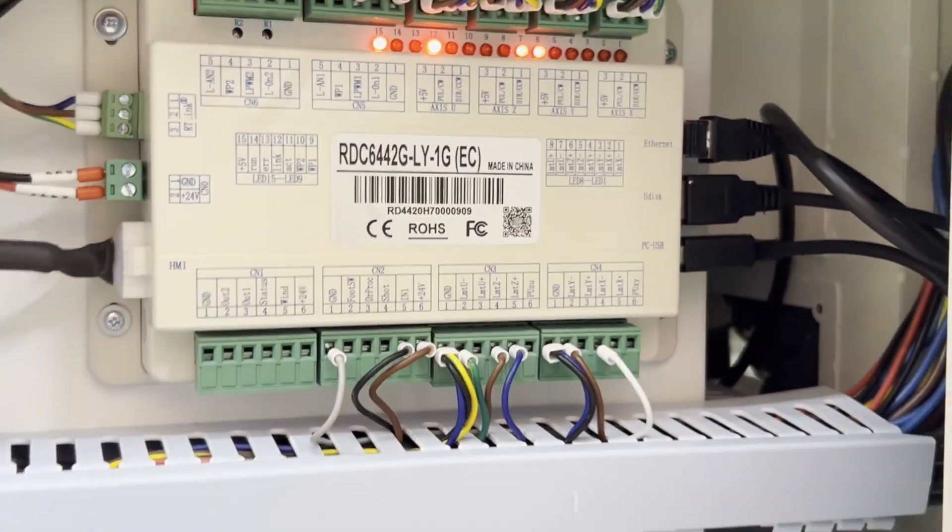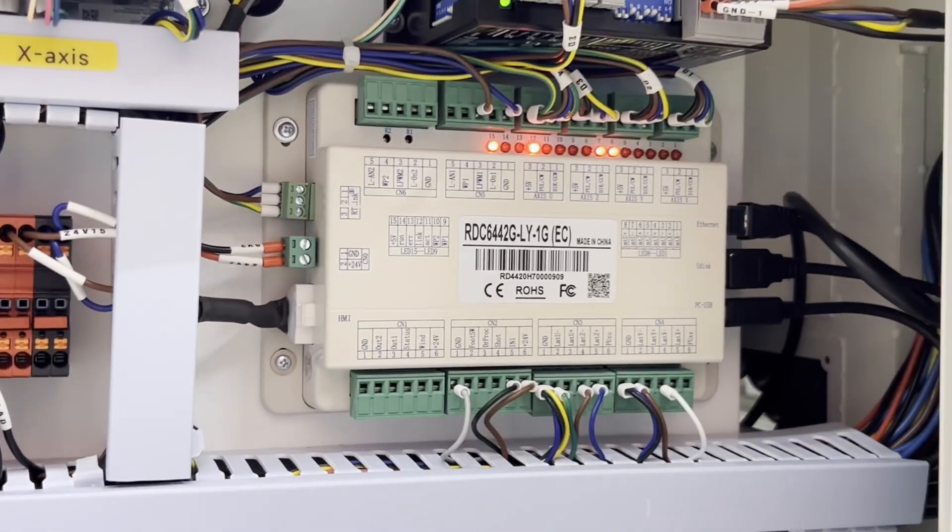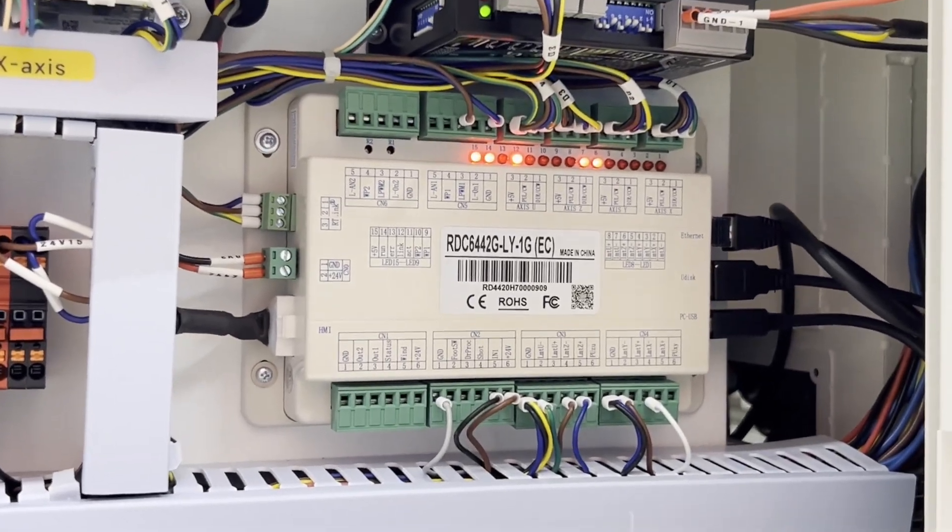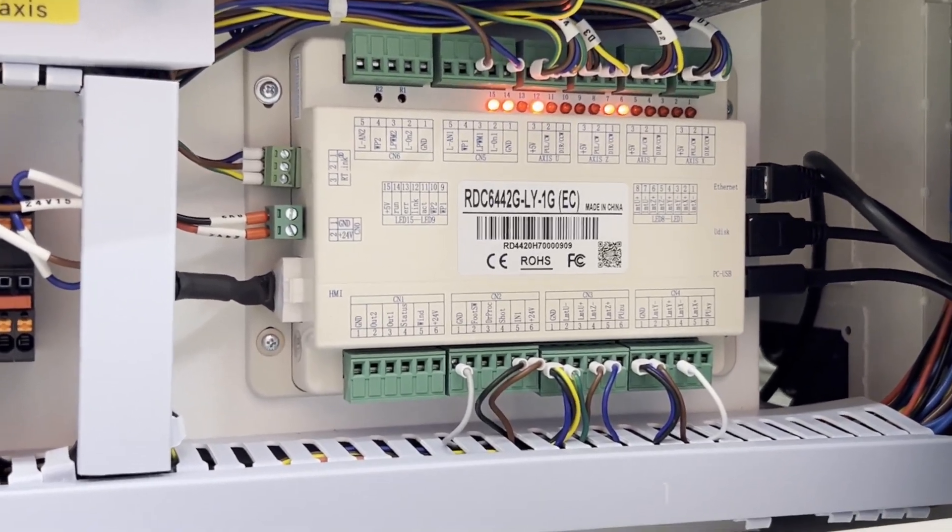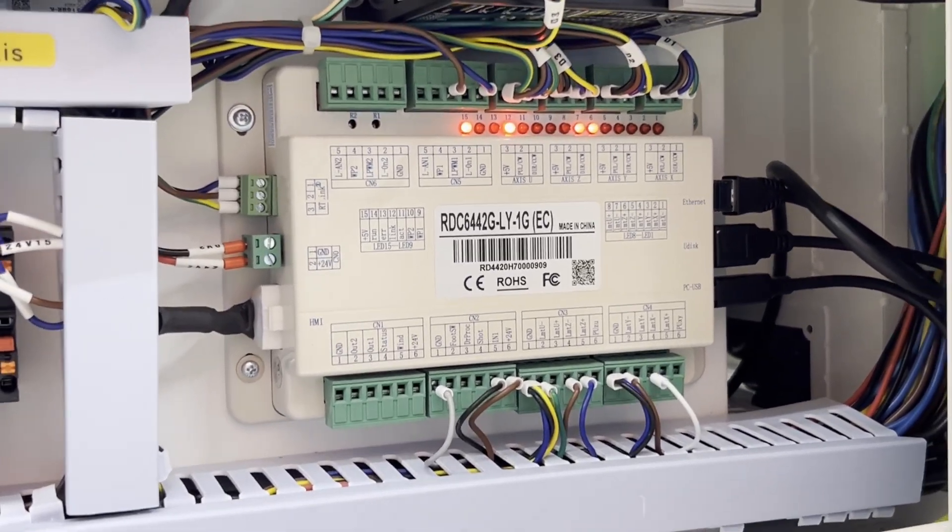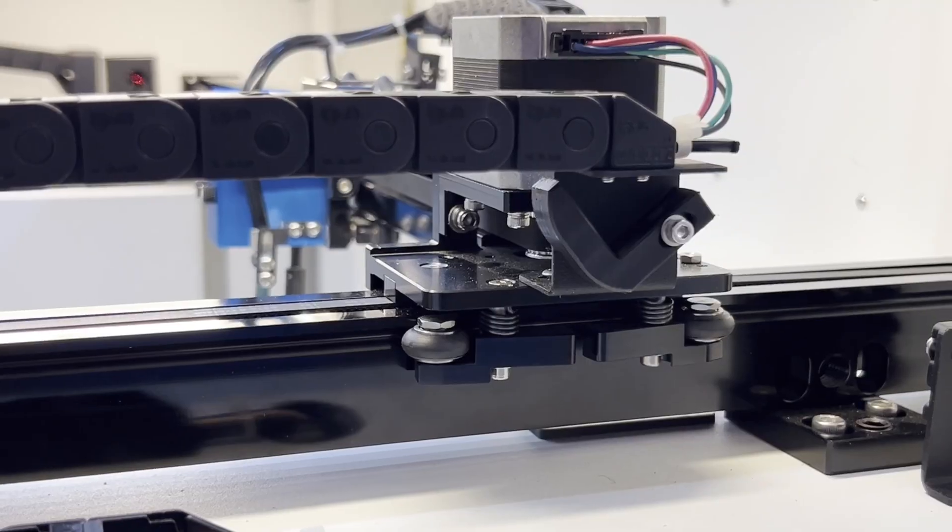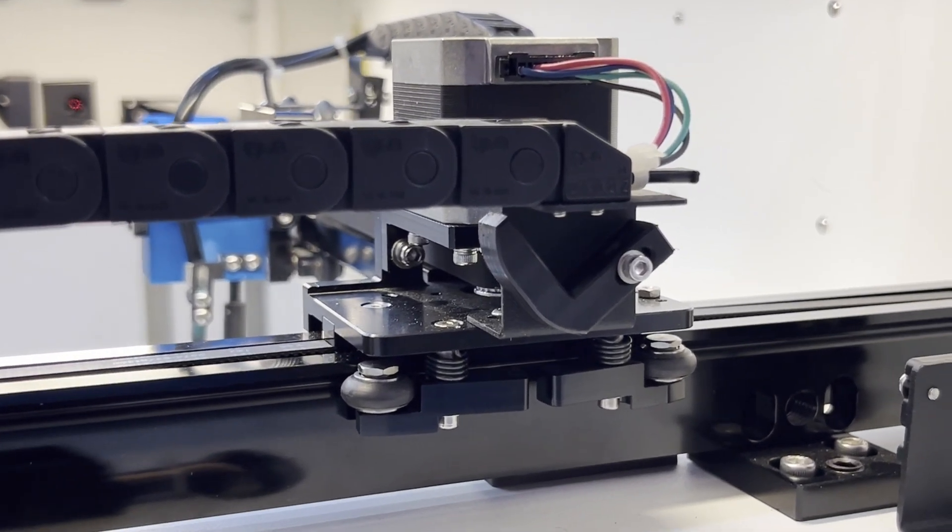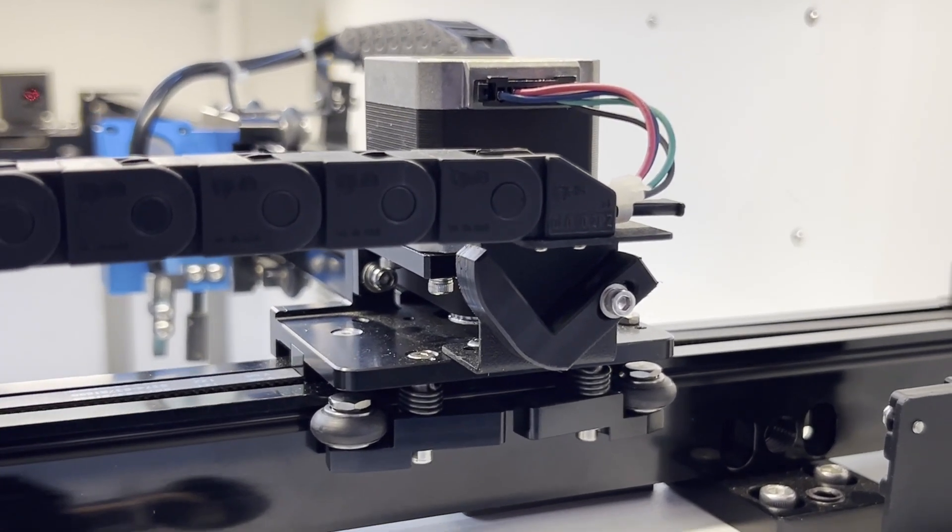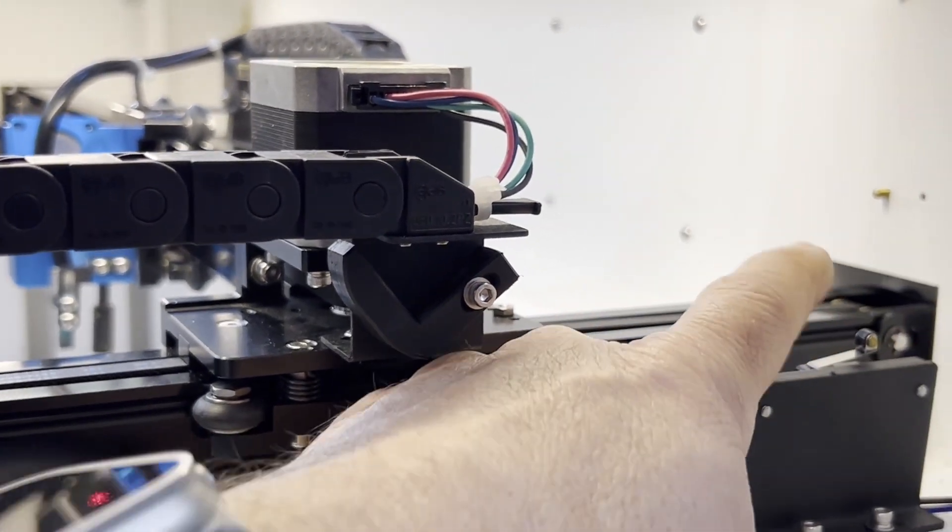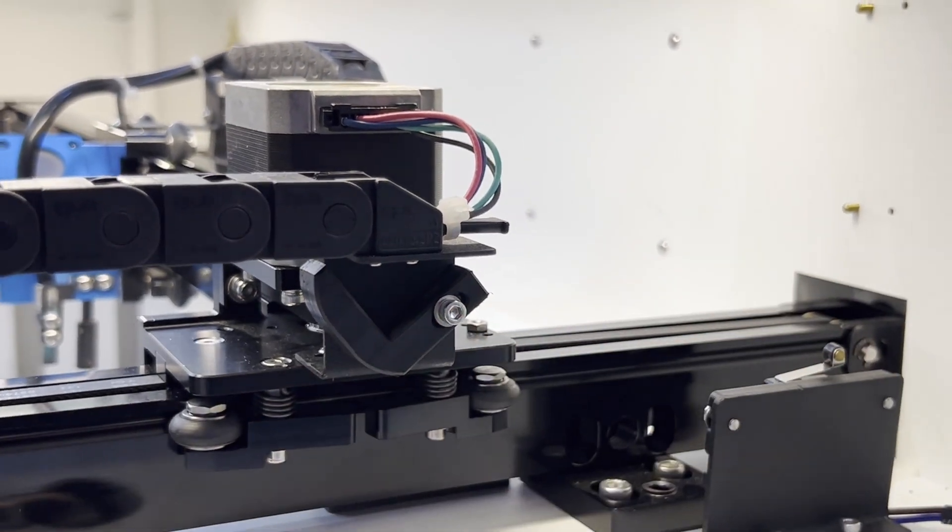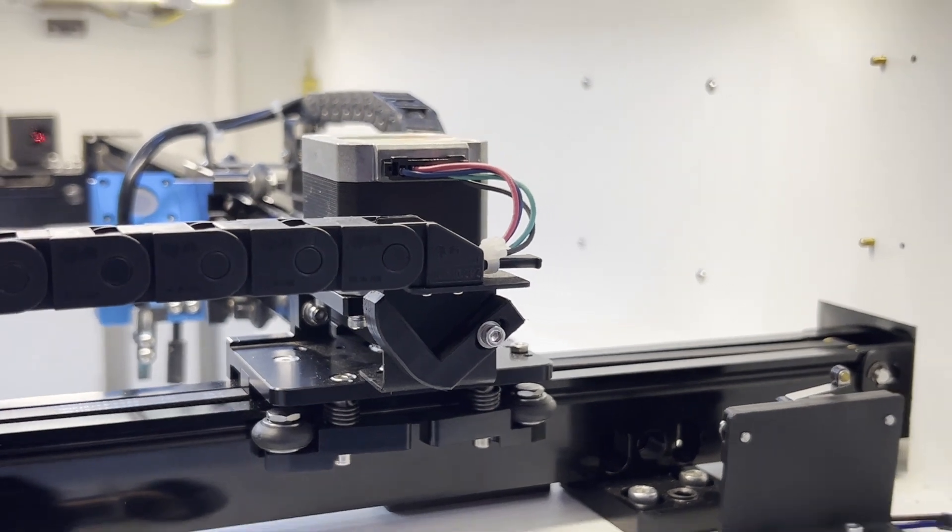And now if I push it in and seat it all the way down, now it's working again. So there are a couple of different places we can check to see where the issue might be. But the most common one is we were cleaning, this got knocked out of the way and it's no longer hitting our switch.